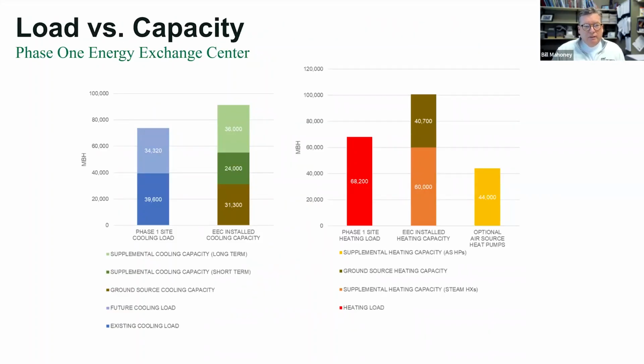And then this goes to show you, like we said, a good portion of those high rises didn't have air conditioning. So we laid out what we could do with our 750 bores to support ground source heating and cooling. And we could only serve what the air conditioning load was. So their load was only this darker blue here in phase one today. If they went and added the cooling to the residences that don't have it, we would get up to this point. But even still, that's the load the buildings required.